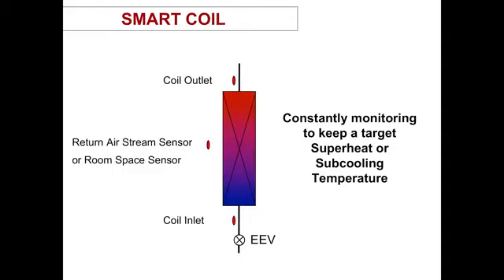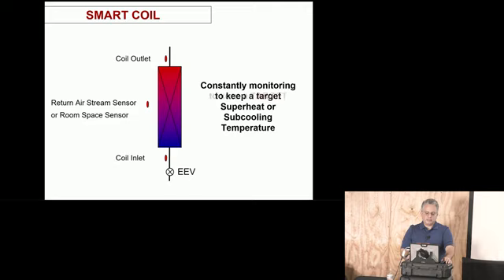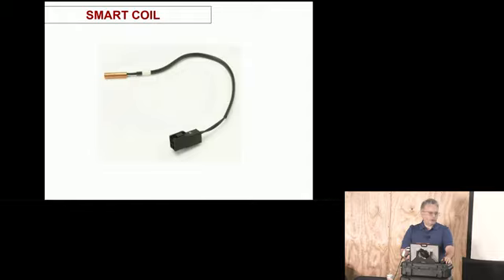Then you have what can be referred to as a smart coil. Some coils have up to 3 sensors in them: an inlet, an outlet, and then a room temperature sensor that's constantly monitoring to keep target superheat or subcooling in line. Key word here is target.